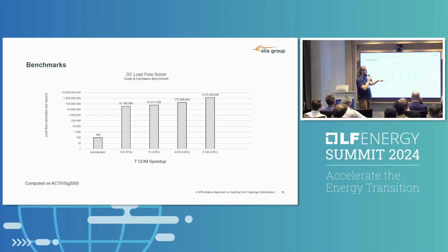And we went from 100 load flows per second in Pandapower. So Pandapower is a grid modeling software. Some of you might know it. If you use run DCPP, you can do that 100 times per second. Well, it's already quite a lot of load flows. Just taking the BSDF idea, and this is log scale, by the way. So who doesn't know log scales? That's a lot. So just taking the BSDF idea got us into the tens of millions of load flows per second, under changing topology.